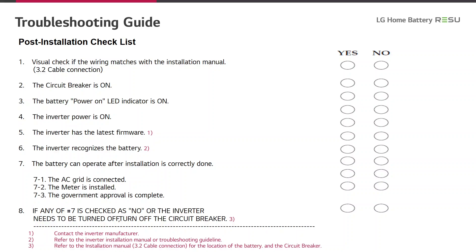On this slide, we have a checklist for you to verify whether your installation has gone right. First, make a visual check if the wiring matches the installation manual. Then check if the circuit breaker is in the on position. The battery should show by LED indicator that it is in the on position. The inverter power should also be showing on position. Please make sure that the inverter has the latest firmware. The inverter should recognize the battery. The battery can operate after installation is correctly done — the preconditions are that the AC grid is connected, the meter is installed, and all legal requirements are complete.